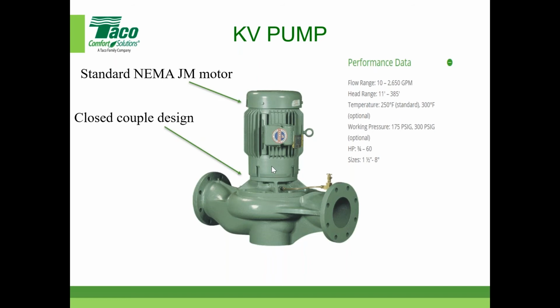Sooner or later, the seal is going to have to be replaced. They're designed to last 7 to 10 years, if not longer. In the right situation and application, with clean water going through there, you should be fine for at least that long. There's a little flush here going through, so that's something to consider.